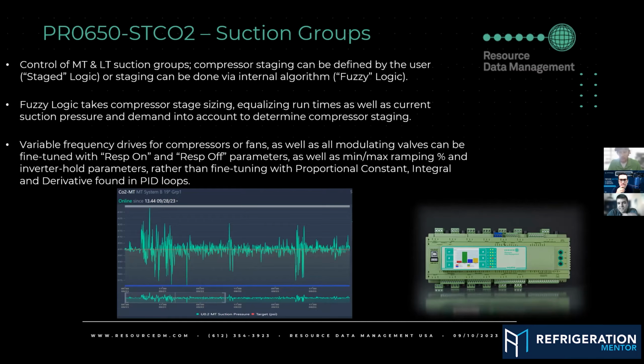Yeah, so you'll see it in suction groups, and that's going to refer to your VFD. If you see it in a gas cooler group, it might respond to your gas cooler fan output or the valve or the receiver valve. There are settings for all of those things in there. You'll also see it in case controllers, where you can dial it in for valves. So it's a way to dial it in without having to change the PIDs. Right. Yep. Because most control manufacturers I talk to say the PIDs do not really have to be touched.